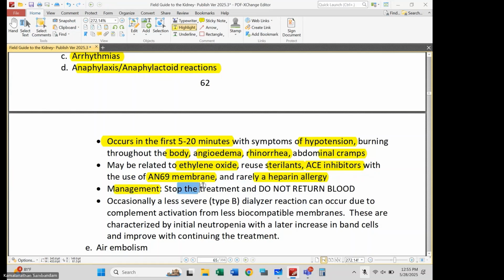Management involves stopping the treatment. Don't return the blood, because the returned blood could further worsen the reaction. Now, occasionally you may have these so-called type B dialyzer reactions. That can happen as a result of complement activation, for membranes that the individual may have biocompatibility issues with. These can be pushed through. Okay, so if you have frank hypotension or angioedema, you're not going to want to try and push through those. You stop the treatment, don't return the blood, and the patient typically recovers.